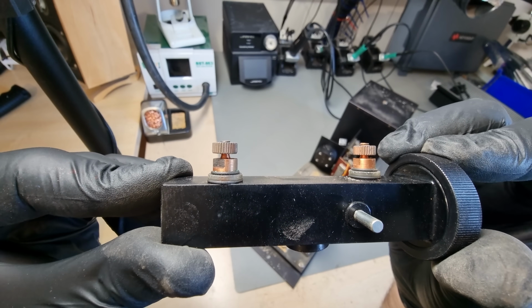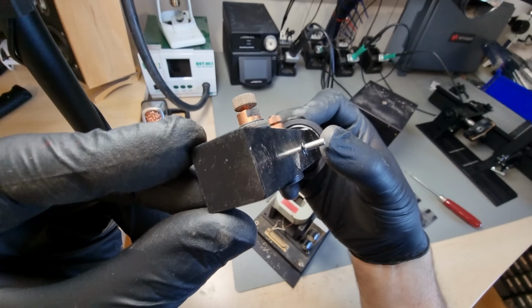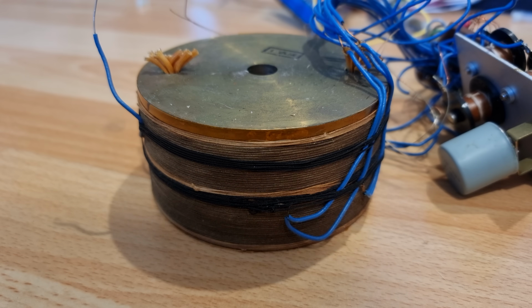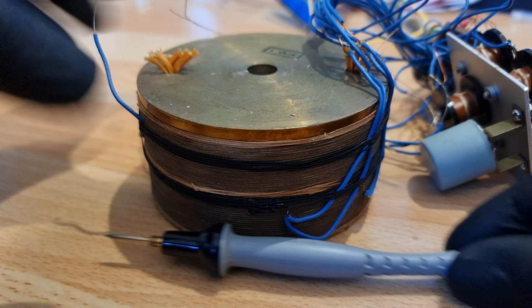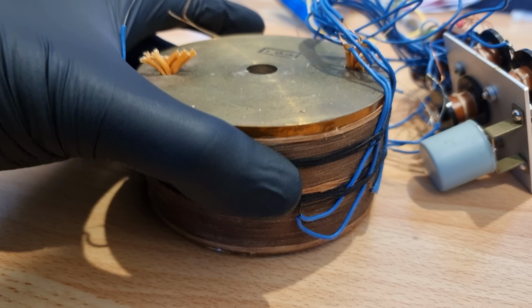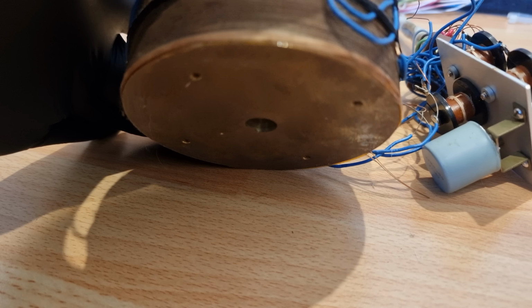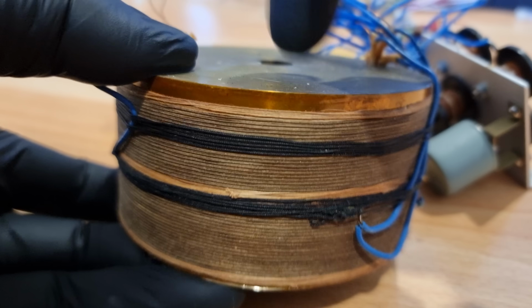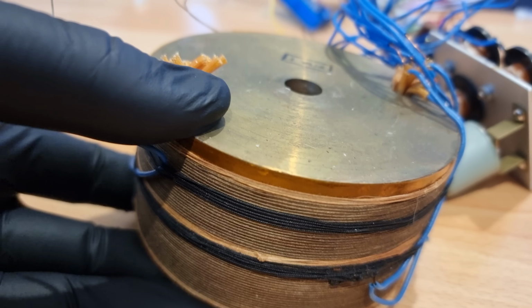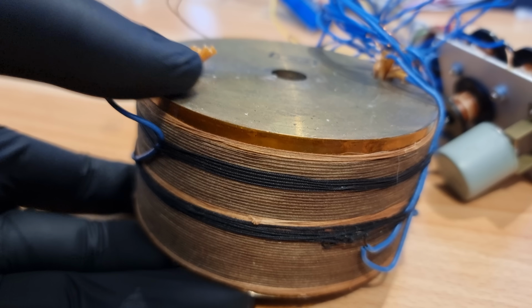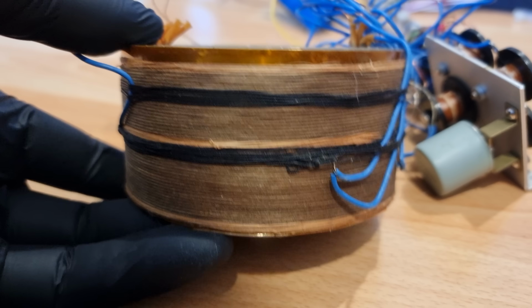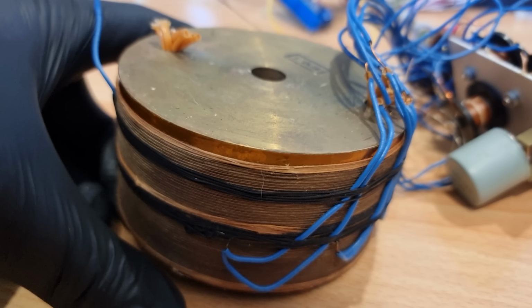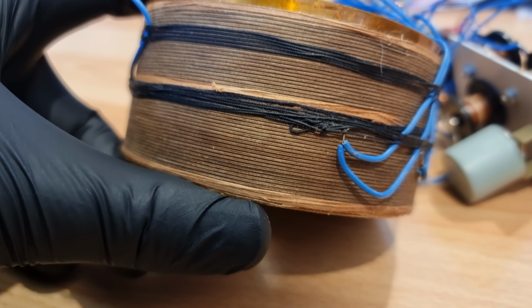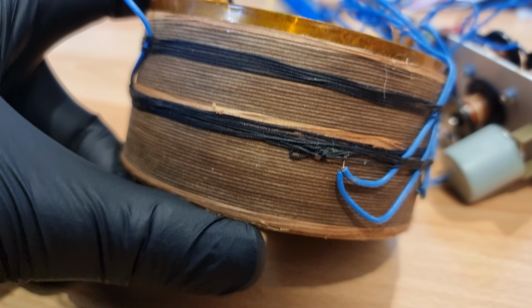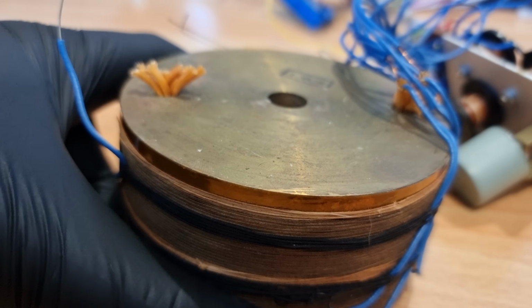Delicious pure copper low thermal EMF terminals. I might have to retract my previously expressed doubts about power coefficient of the forcing resistors posing a risk to linearity, because this solid few kilogram brass chunk appears to be home to the all-important forcing resistors. They are just wire wound around the perimeter, providing excellent thermal coupling and a gigantic time constant, plus temperature coefficient of thermal expansion of brass and manganin wire should be very nicely matched.